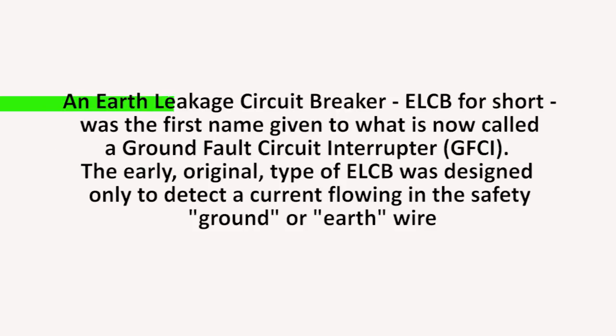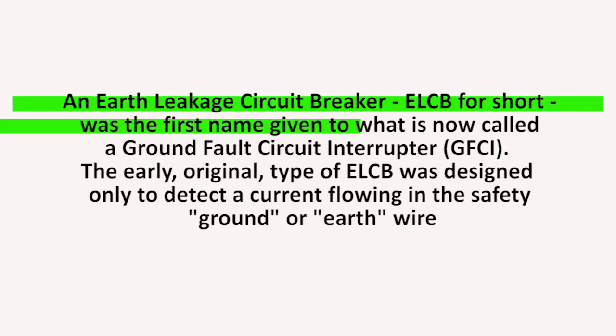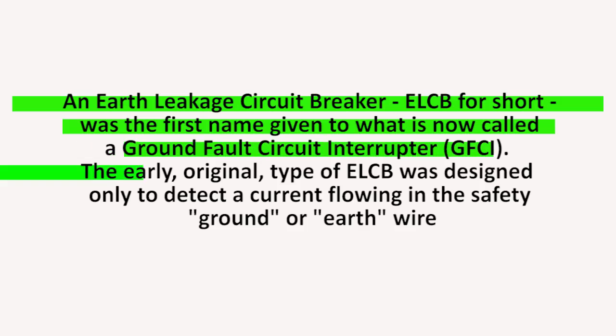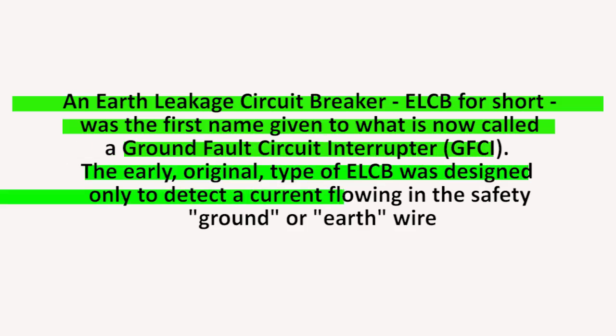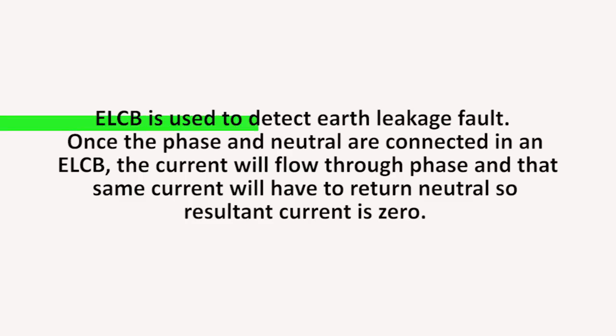अर्थ लीकेज सर्किट ब्रेकर, ELCB for short, was the first name given to what is now called a ground fault circuit interrupter, GFCI. The original type of ELCB was designed only to detect a current flowing in the safety ground or earth wire. ELCB is used to detect earth leakage fault.